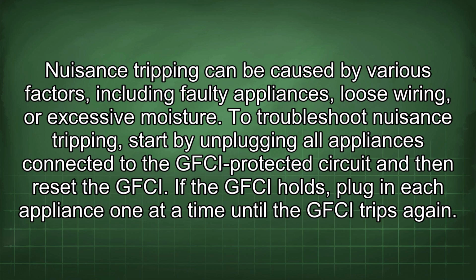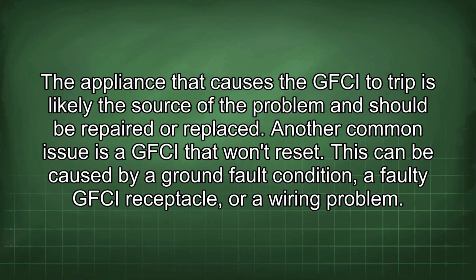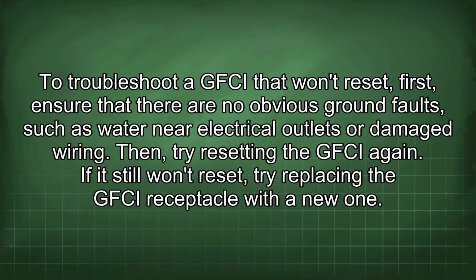To troubleshoot nuisance tripping, start by unplugging all appliances connected to the GFCI protected circuits and then reset the GFCI. If the GFCI holds, plug in each appliance one at a time until the GFCI trips again. The appliance that causes the GFCI to trip is likely the source of the problem and should be repaired or replaced. Another common issue is a GFCI that won't reset. This can be caused by a ground fault condition, a faulty GFCI receptacle, or a wiring problem. To troubleshoot a GFCI that won't reset, first, ensure that there are no obvious ground faults such as water near electrical outlets or damaged wiring.